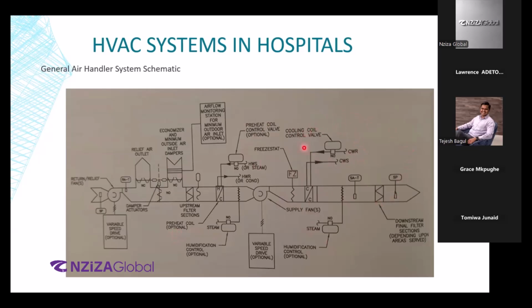Next thing is the cooling coil. Of course, when you have heated it, the air will be quite hot. And then you need to cool it down if in case the supply air temperatures are not being met at this point of time. If required, you can have another humidification coil over here that is based on steam. Then you'll have a thermostat over here for measuring the supply air temperature.